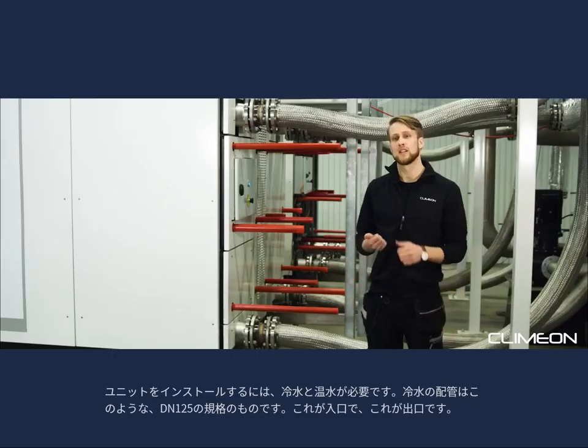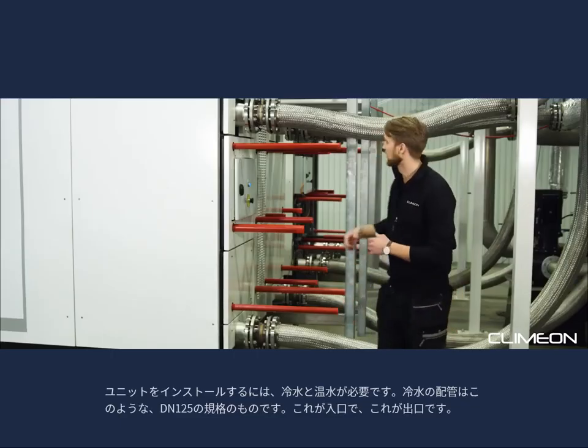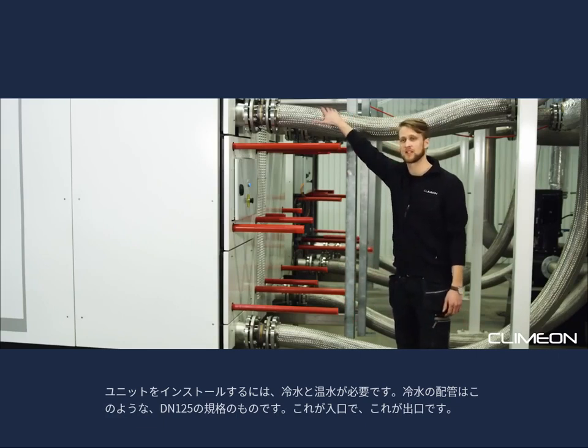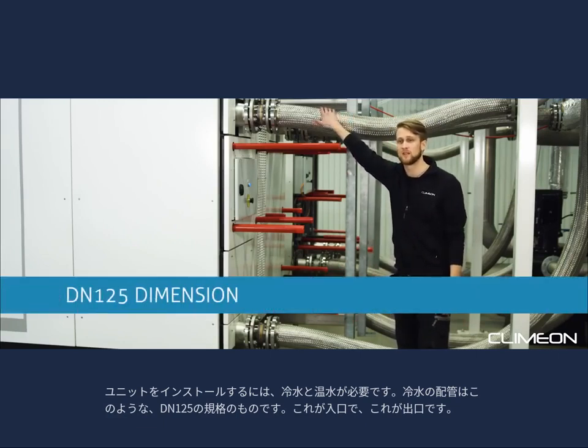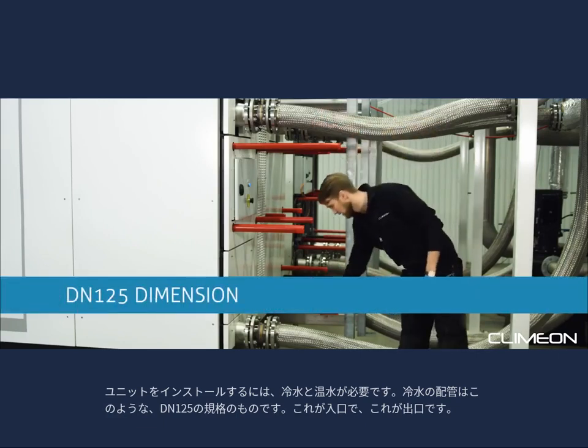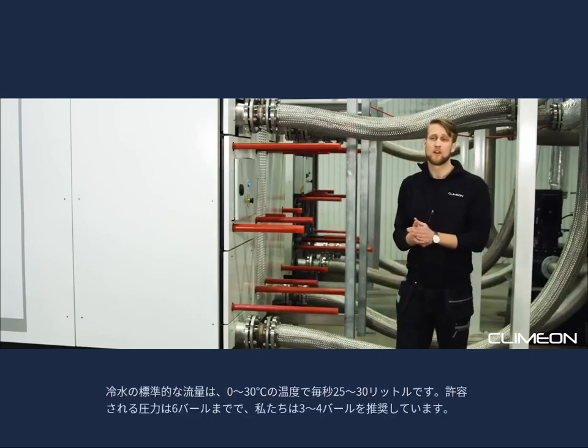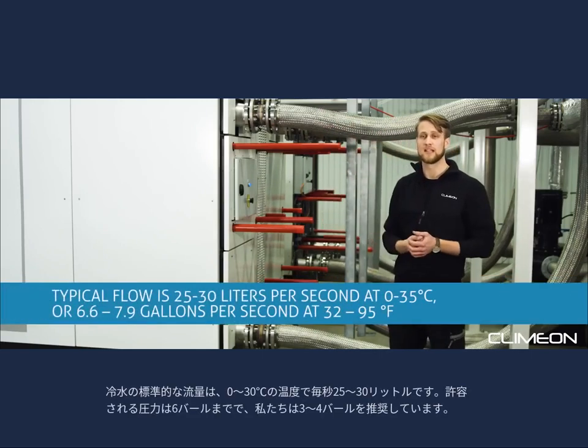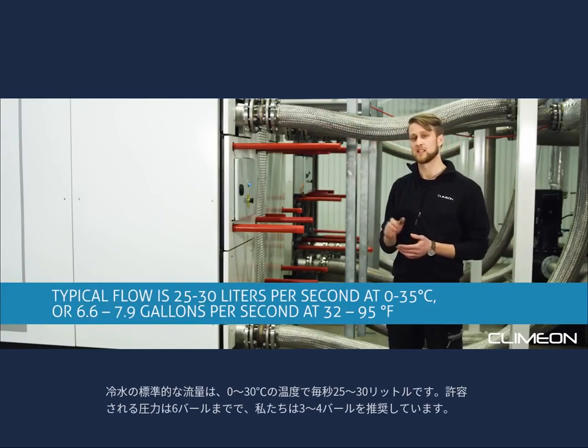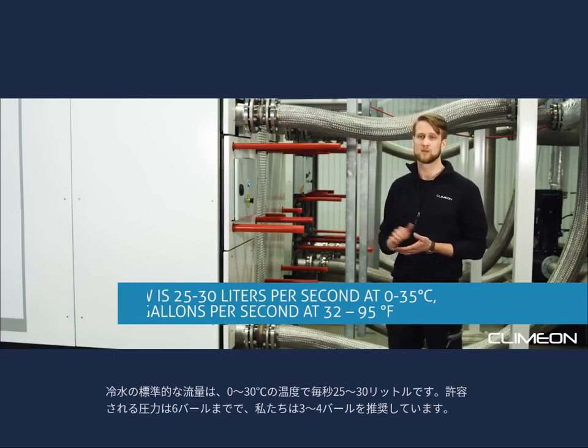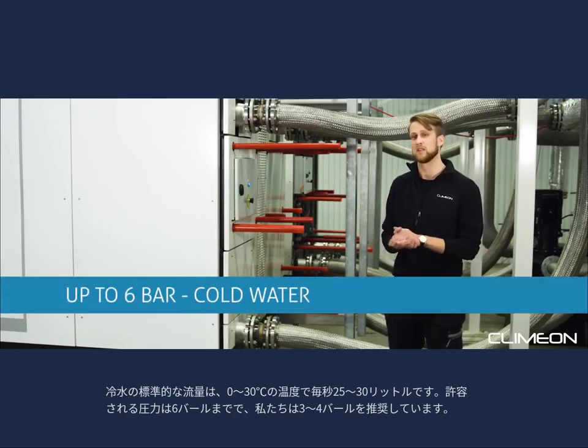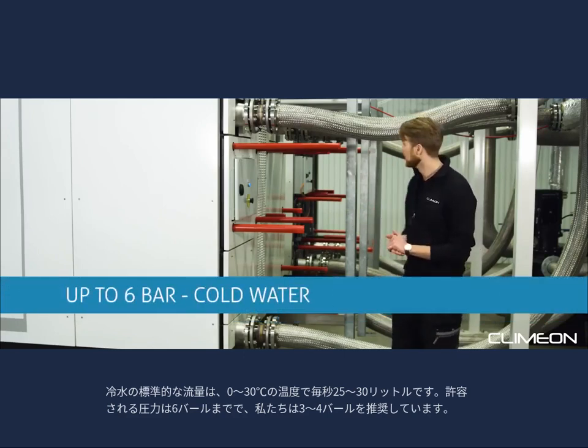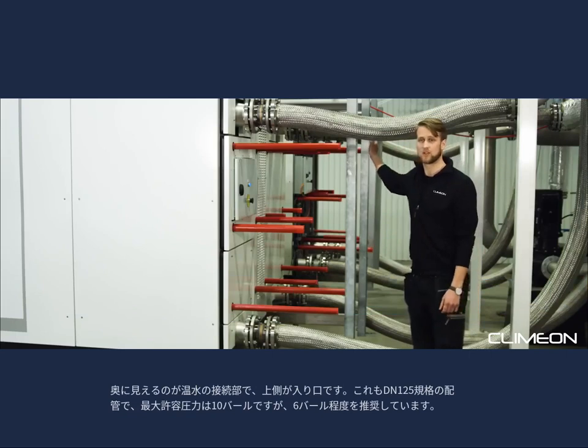To install the units, you need cold water and hot water. So the cold water piping is the one you can see here. It's a DN125 dimension. This is the inlet and this is the outlet. The typical flow for the cold water is 25 to 30 liters per second at a temperature between 0 and 35 to 40 degrees Celsius. And the pressure that we allow is up to 6 bar, and we recommend around 3 to 4 bars. In the back you can see the hot water connections.